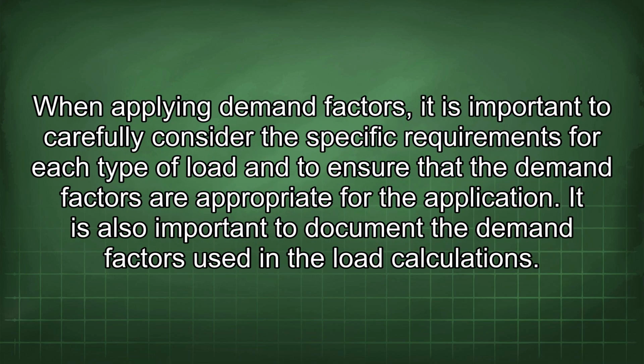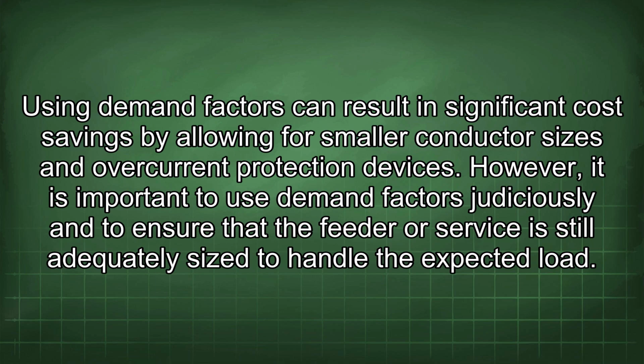When applying demand factors, it is important to carefully consider the specific requirements for each type of load and to ensure that the demand factors are appropriate for the application. It is also important to document the demand factors used in the load calculations. Using demand factors can result in significant cost savings by allowing for smaller conductor sizes and overcurrent protection devices. However, it is important to use demand factors judiciously and to ensure that the feeder or service is still adequately sized to handle the expected load.